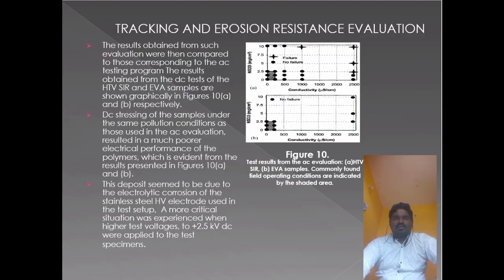Hello, myself Adarsh Naik. I will be explaining the test results based on tracking and erosion resistance evaluation on HTV, SIR and EVA samples, and epoxy resins, followed by results and conclusions. HTV SIR stands for high temperature vulcanized silicone rubber insulators, and EVA stands for ethylene vinyl acetate. The results obtained from the DC test of the HTV SIR and EVA samples are shown graphically in figures 10A and 10B respectively.